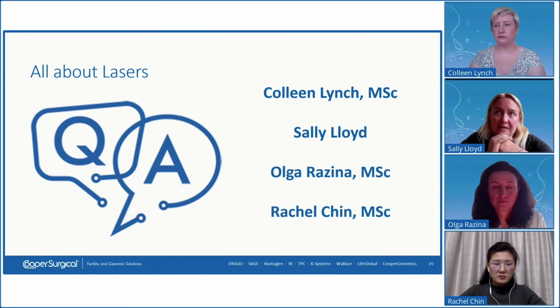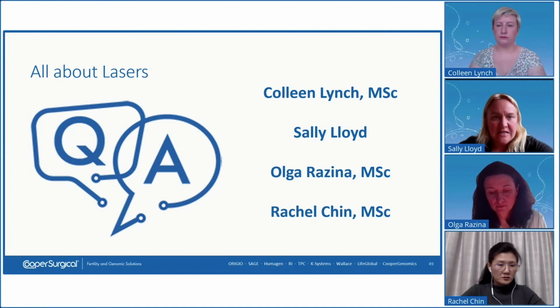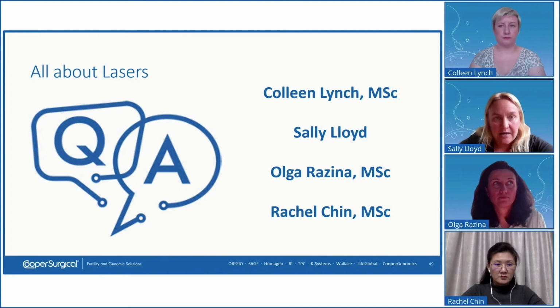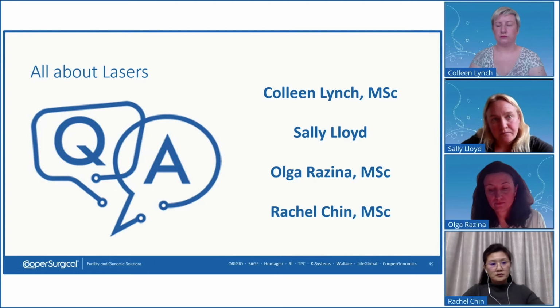In some cases, often when a laser has been moved either from one microscope to the other, or moved location around the lab, sometimes you shuffle the lab around to make it more efficient, then dirt can get inside the laser, and it can sap the laser energy coming from the laser box. In which case, there's nothing really that the user can do about it, but an engineer could come in and clean it. Or it would have to come back to us to be cleaned down.